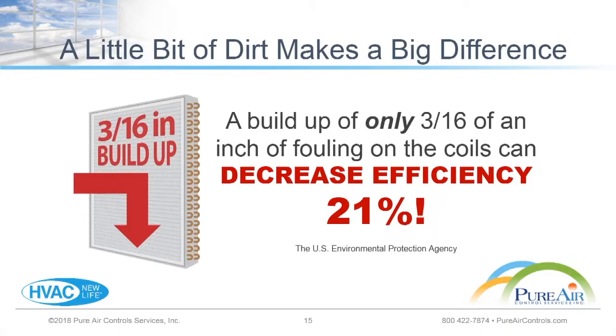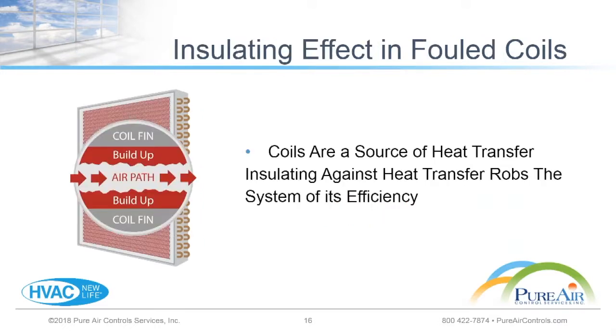It only takes a very small amount, about 3/16 of an inch of buildup on coils, to decrease efficiency by 21% of the air handler system. Just food for thought. The reason is straightforward: the coils are the source of heat transfer, and insulating against that heat transfer robs the system of its efficiency. We're talking about anything that can attach to the coil surface, whether it's dirt, grease, dust, corrosion, even tobacco smoke. So we're talking about human health effects, energy efficiency, and of course the microorganisms that can attach.